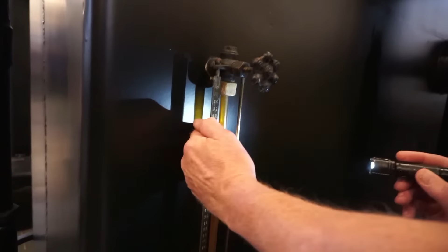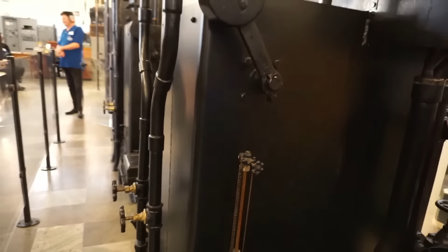Here are 3 rheostats. This is a backup. They are used to control the speed of the motor. The start rheostat is used to control the torque to the motor when we are starting up. Later on, we use it to fine-tune the motor speed. It is connected to the rotor in the main motor by slip rings and cables.